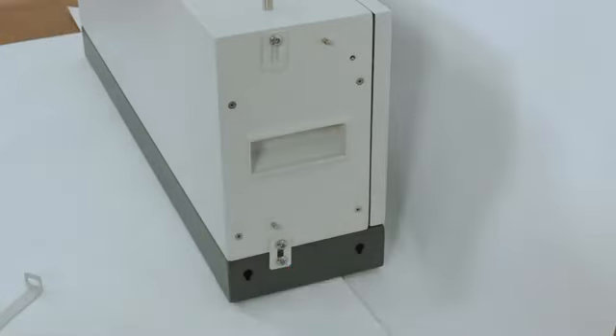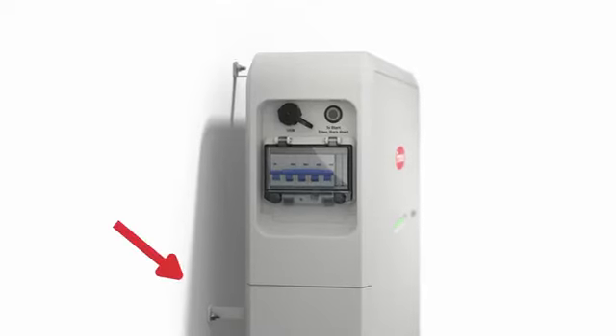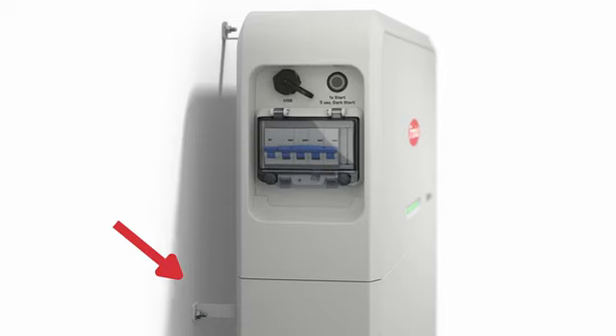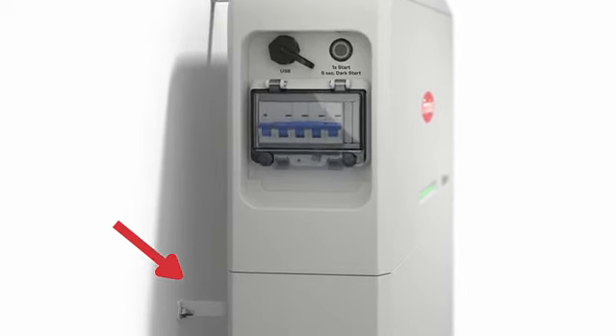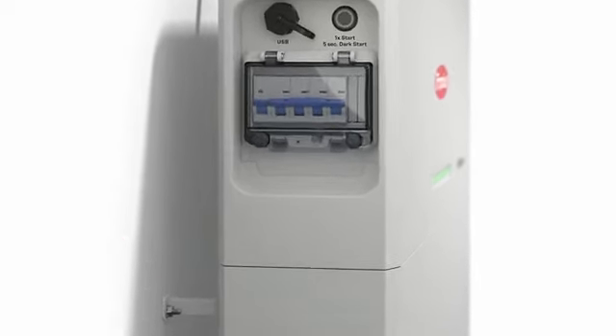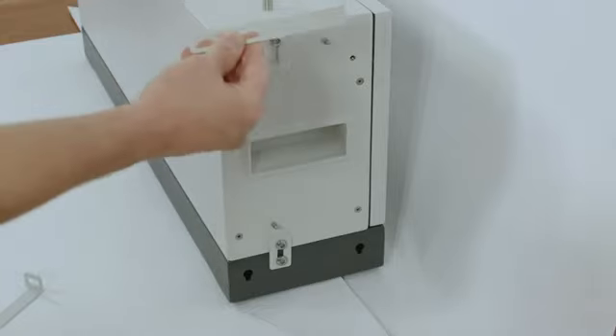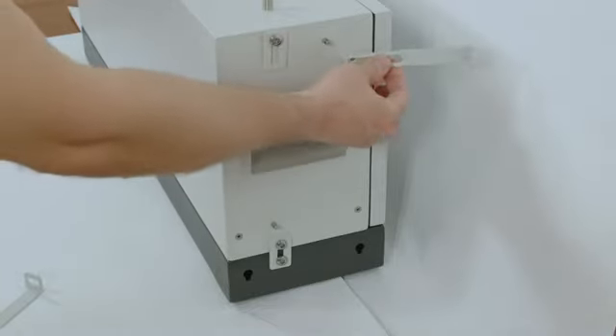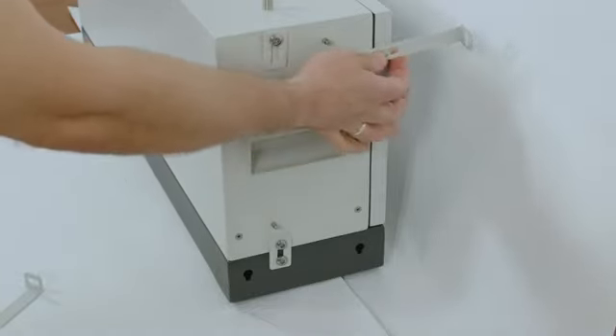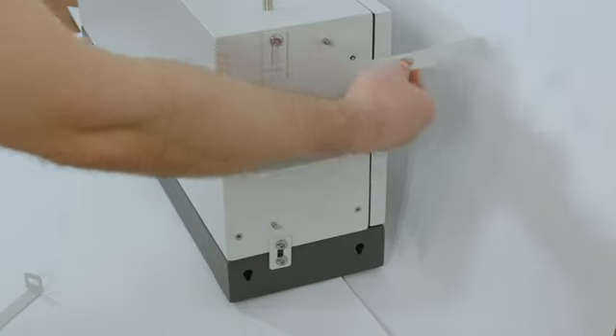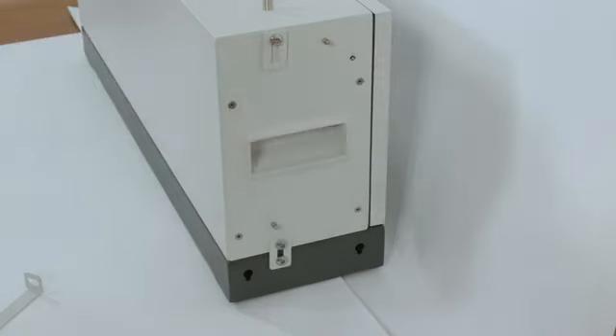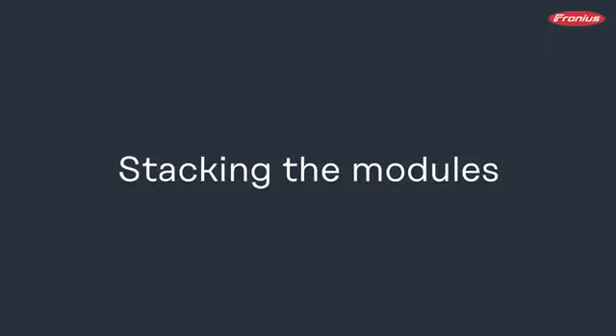To fix the battery to the wall and avoid it from tilting, please make sure to use the wall mounting system from the scope of delivery. With this wall mounting system, you will find some mechanical screws to screw it to the wall, as well as a wall mounting bracket that can be placed on the battery module and be connected to the wall. Please make sure to connect at least every 2 modules to the wall.